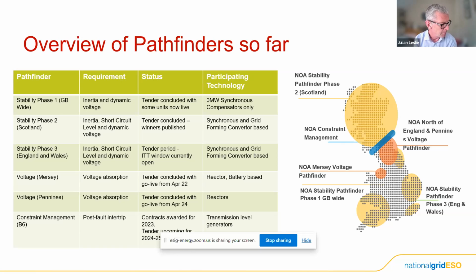Phase two, though, is the one we've been really excited about. Phase two was for short circuit infeed in Scotland. Phase two coincided just after we'd put grid forming inverters into our grid code here in Great Britain, which I believe is the first in the world. It's back to Mark's chicken and egg process. I believe in GB we've broken the chicken and egg cycle in that we now have a minimum viable product for a grid forming inverter on the system.